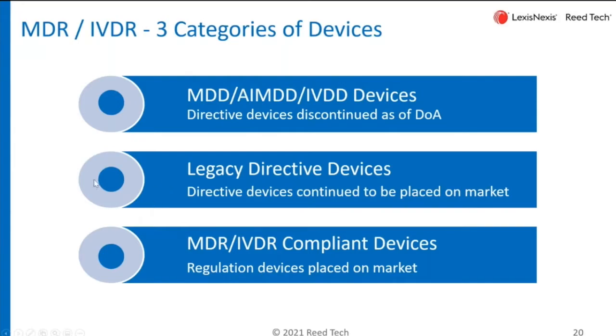Most items in your portfolio are likely legacy directive devices — devices you're currently placing on the market and would like to continue placing after the date of application. There is a transition period of two to three years, depending on whether it's an MDR device or in vitro diagnostic. A couple of criteria apply: the certificate must be valid and not expired, and there can be no significant design changes. As you meet those criteria, you're able to continue placing them on the market, but you do have to register these devices within a specified time period.